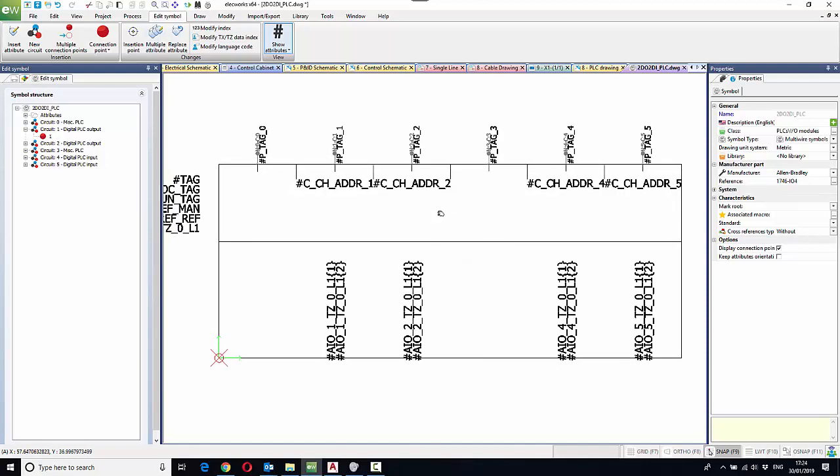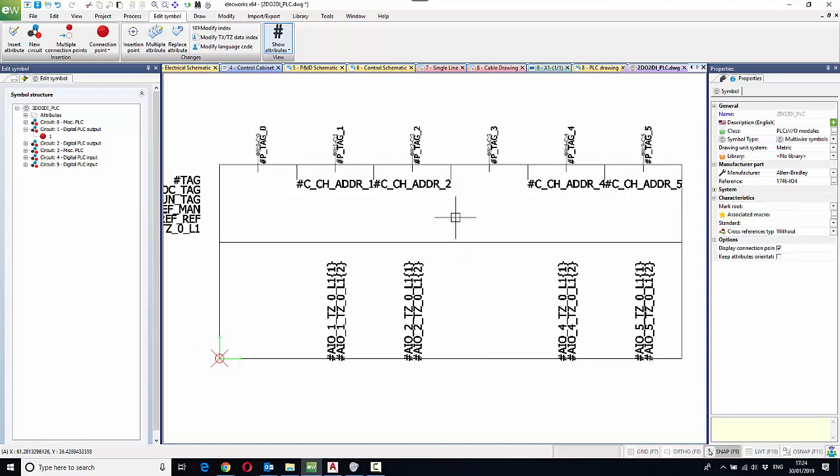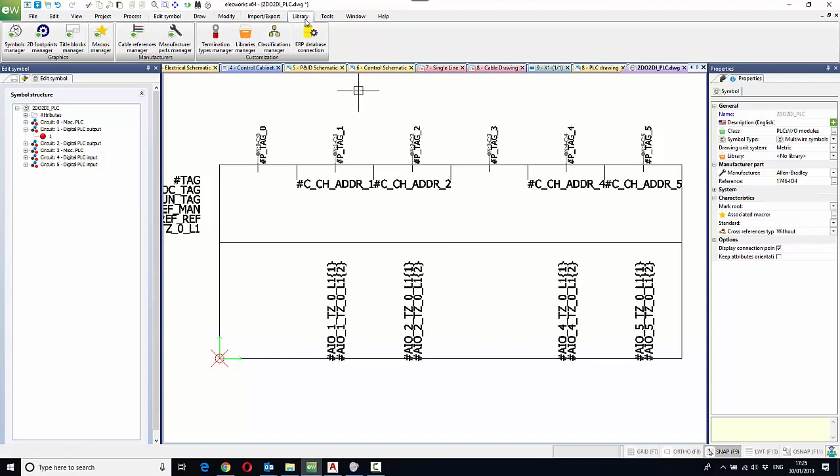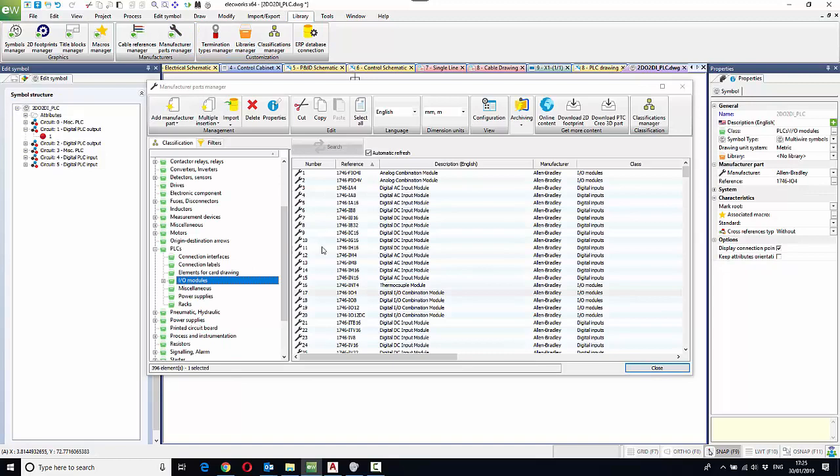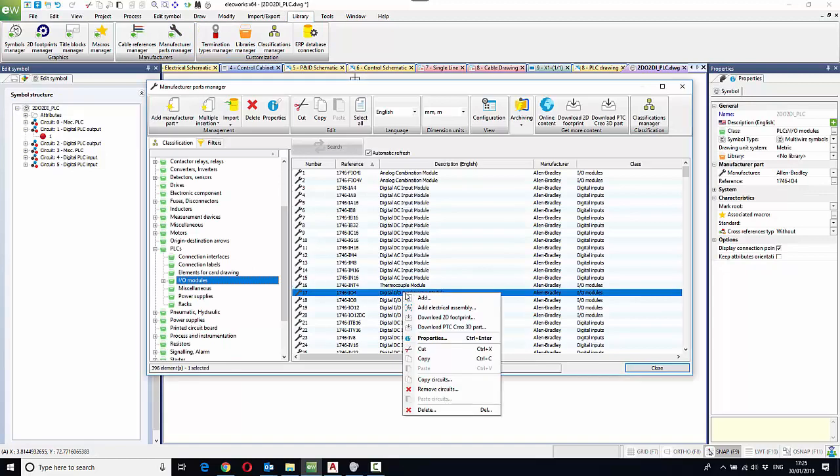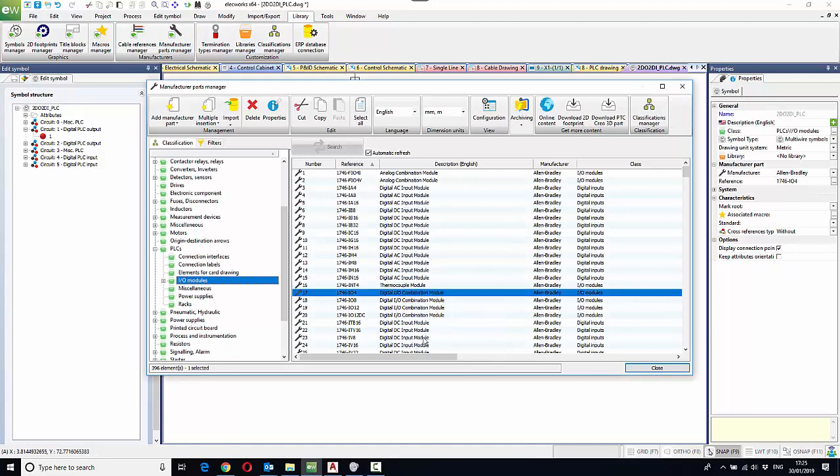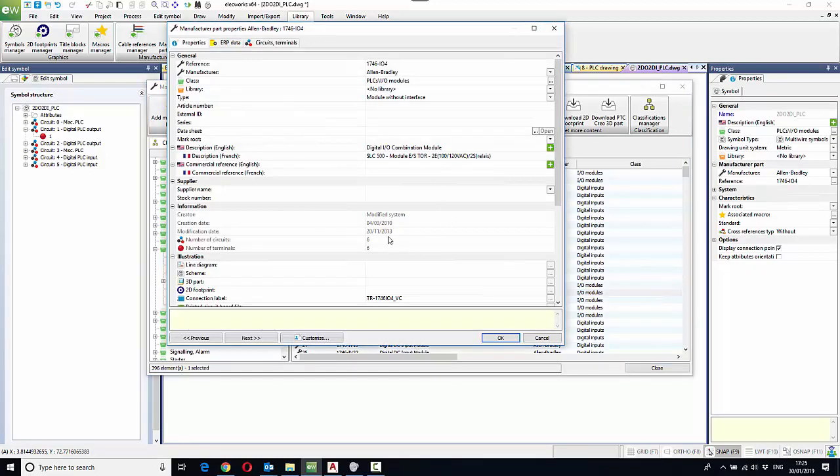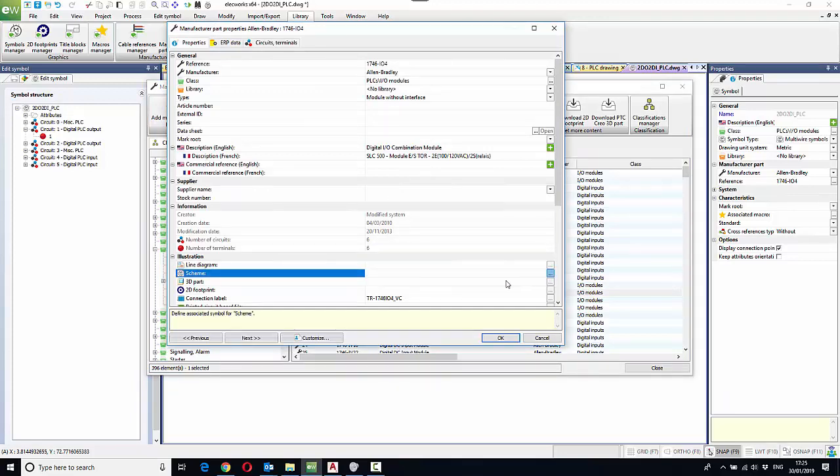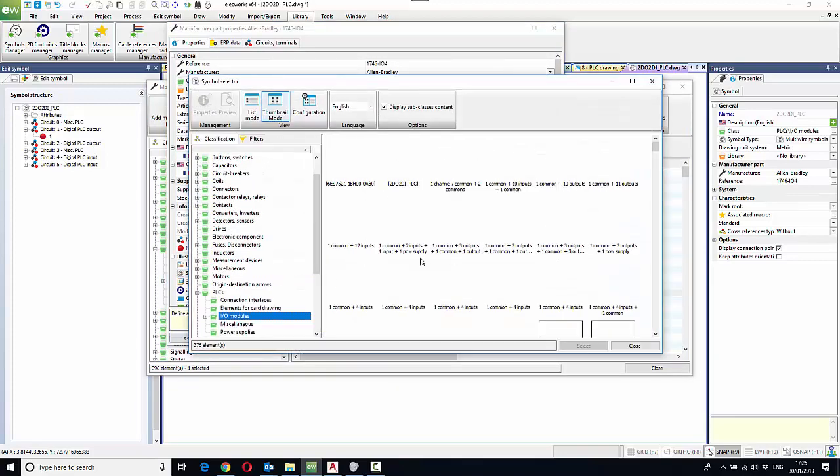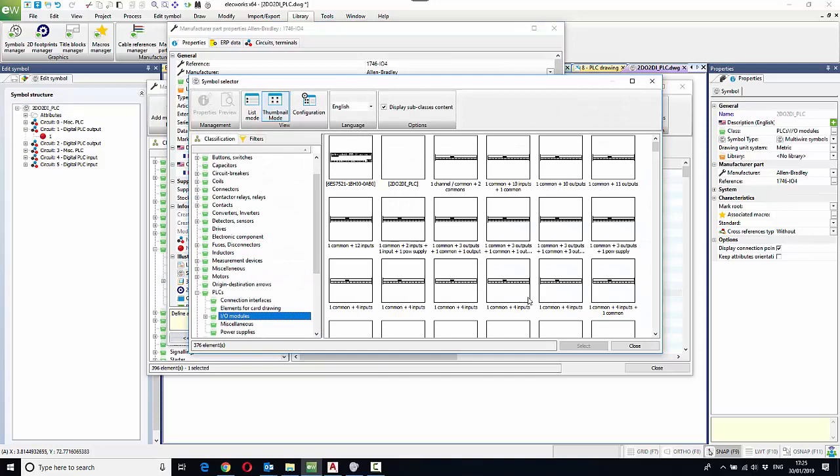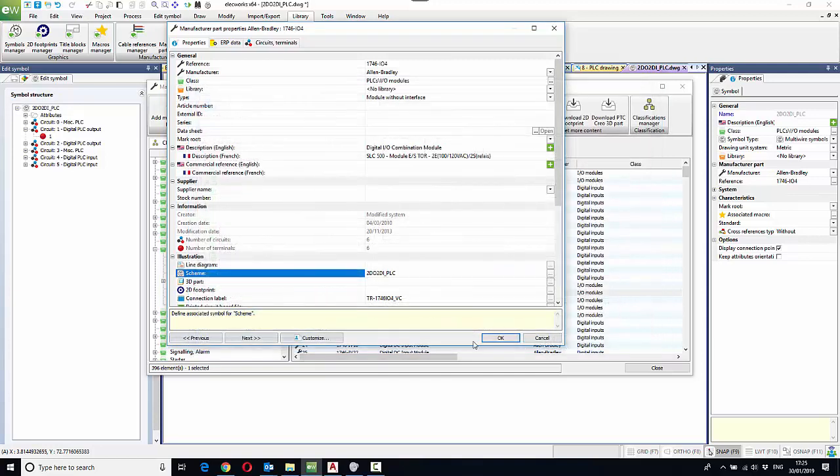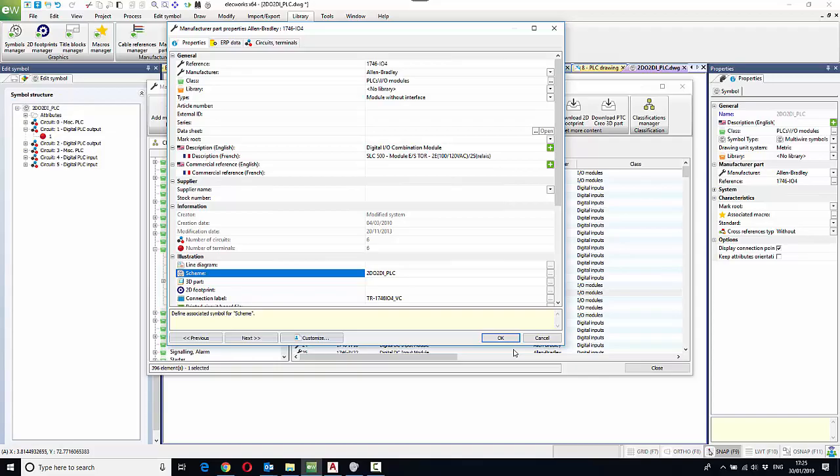That is our PLC symbol done. All we've got to actually do is go back to our library, back to the manufacturer's part, and change the properties of this symbol so that the electrical schematic symbol associated is this newly created symbol. And that will be permanently associated. And we'll use this symbol rather than the parametric symbol when PLC drawings are done.